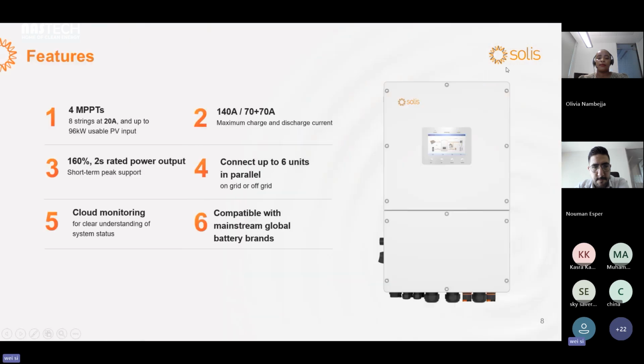Okay, for this inverter, the features: we have 4 MPPTs and we support 8 strings, with a maximum current of up to 20 amperes. For the charging current, we can realize 140 amperes for the battery, and short-term peak support. For parallel mode, we can support up to 6 units in parallel, but we already realized 10 units in parallel mode 3 months ago. We also support cloud monitoring, and we are compatible with mainstream global battery brands.